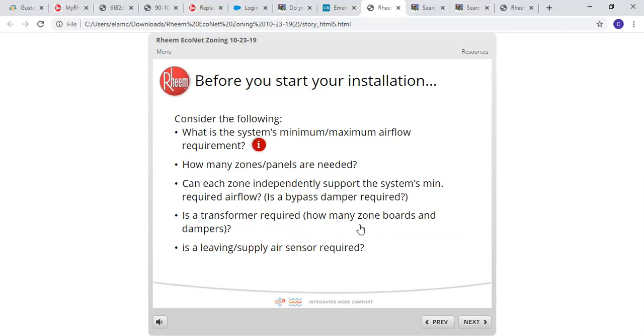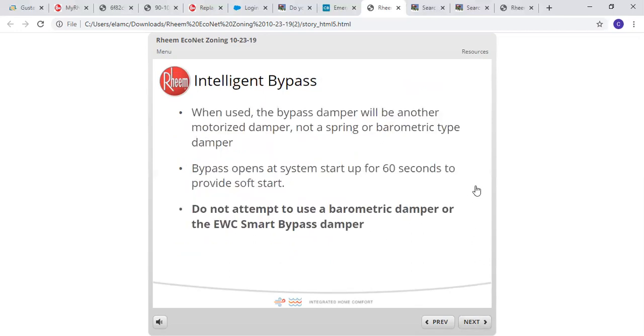And another one: is a transformer required? How many zone boards and dampers? And then is a leaving supply sensor required? They do have what they call an intelligent bypass. When used, the bypass damper will be another motorized damper. It's not a spring-loaded or barometric damper. The bypass opens at system startup for 60 seconds to provide a soft start. And then highlighted here is: do not attempt to use a barometric damper or the EWC smart bypass damper. You're basically going to use whatever size damper you need for your bypass, and your board will actually recognize that it's a bypass and it will throttle it accordingly.